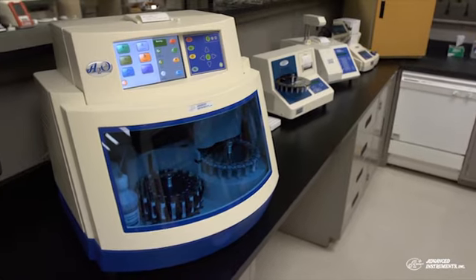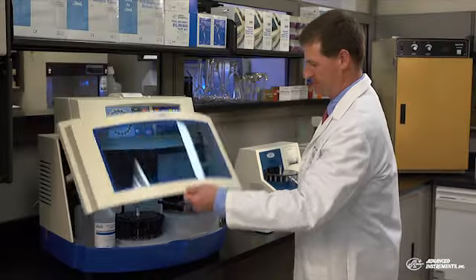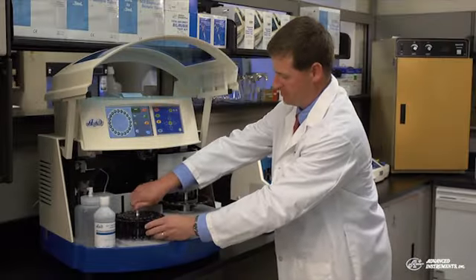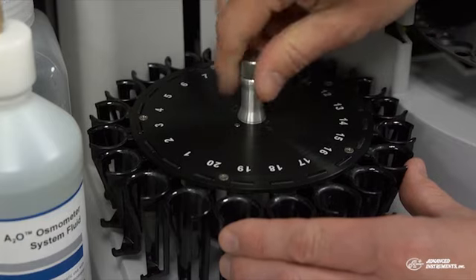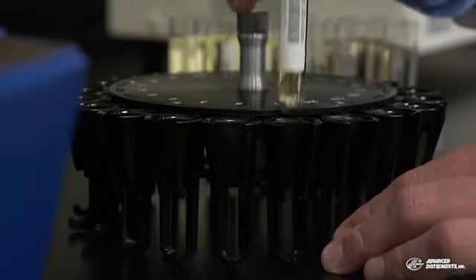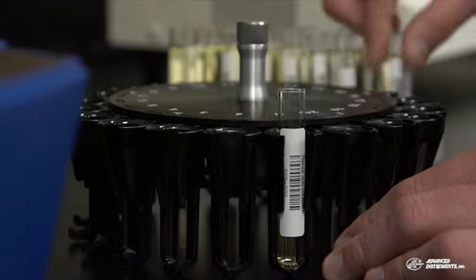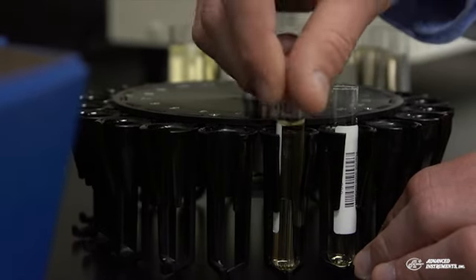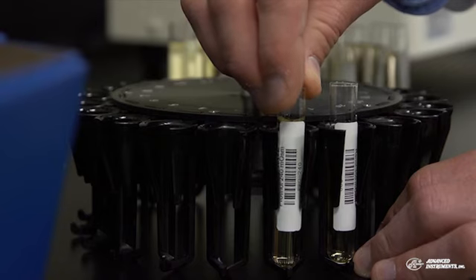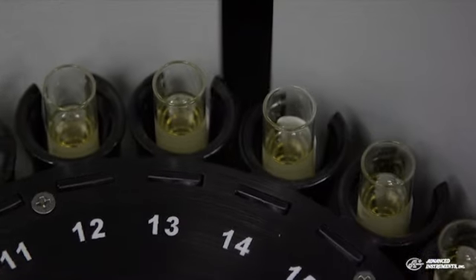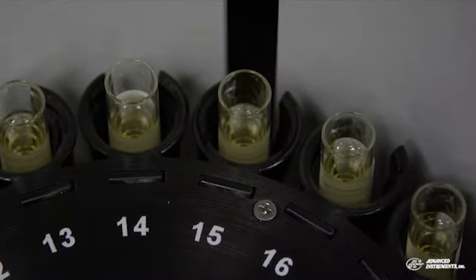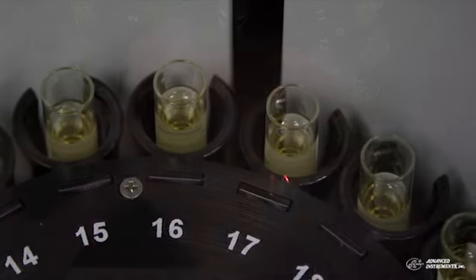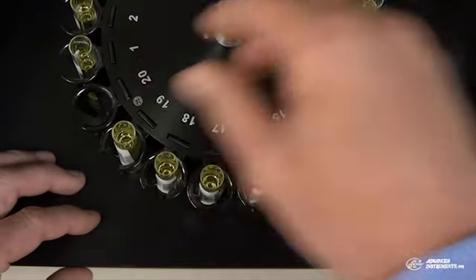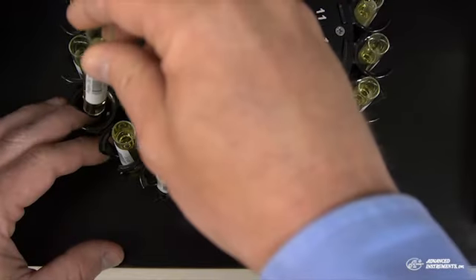Operating the A2O is fast and simple. First, open the A2O access door and remove the primary tube carousel. Load the samples onto the carousel, making sure the caps have been removed and the barcode is aligned between the grooves of the sample tube clip holder. The A2O will automatically scan for the presence of sample tubes and barcodes, so it is not necessary to place the samples in any particular order or location on the carousel. Secure the primary tube carousel back into the system.